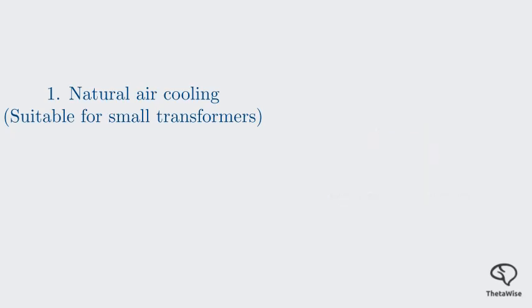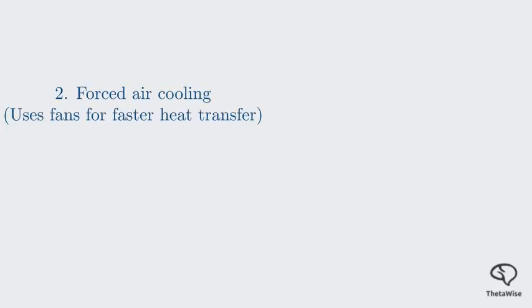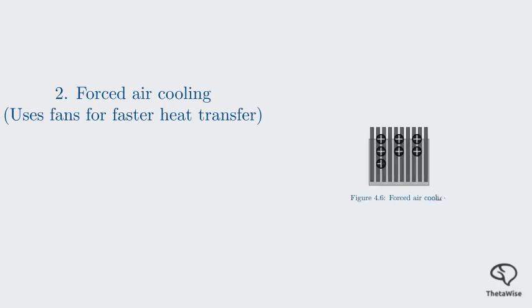For larger transformers, we need more active cooling. Forced air cooling uses fans to move air more rapidly over the transformer's surfaces, which can be the windings and core in a dry-type system, or the cooling fins of an oil-cooled transformer. You've likely seen large industrial transformers with rows of fans attached to their cooling fins, just like the one in Figure 4.6. This method greatly increases the rate of heat dissipation.